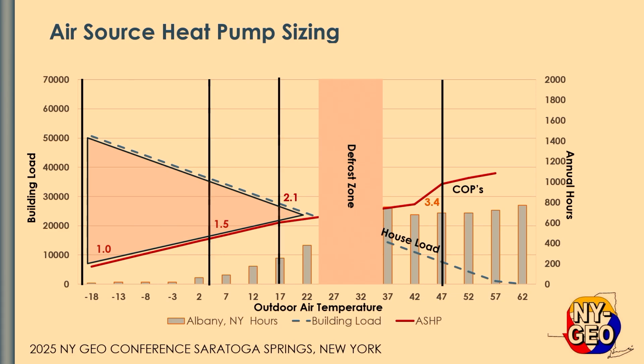And so this particular heat pump that's being modeled here is a 16 SEER, two-stage. I've not shown it exactly the way a two-stage would be, for clarity, but if you recall, you'll have a part load and a full load, but it was going to get a little messy in the slide, so I kept it like it's on full load because we're not really analyzing the operational costs here, but more how it handles low temperature.